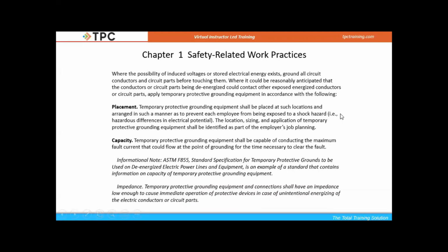This is the last step. The last step tells us that if we do have the possibility of induction or capacitance, then we have to put on what I call a grounding cluster. And this would be put on with a hot stick also. This is a temporary protective grounding device. It has an American Society for Testing and Materials standard, F855, that tells us that it does have to have the capacity to be able to carry the maximum fault current.